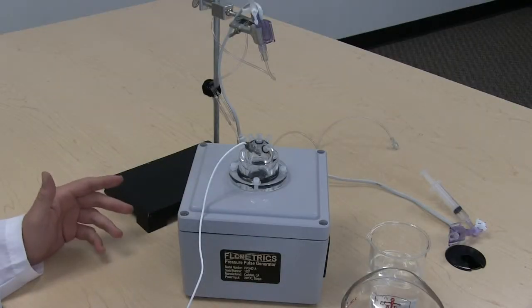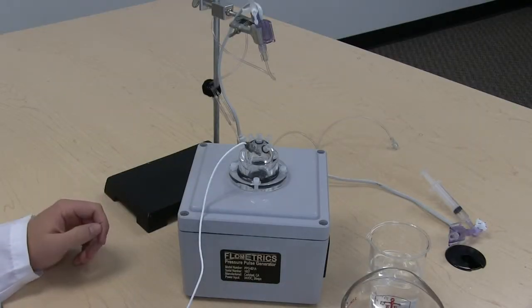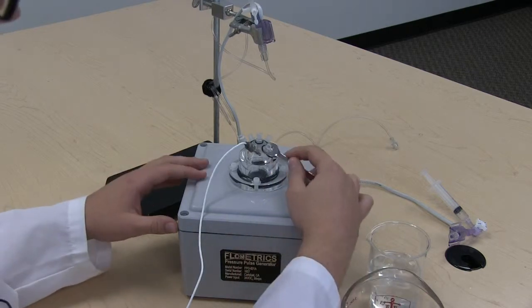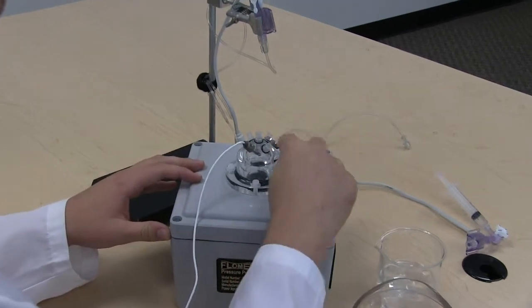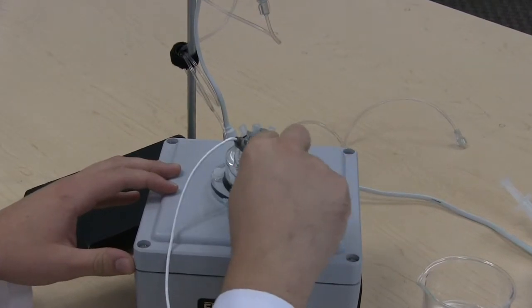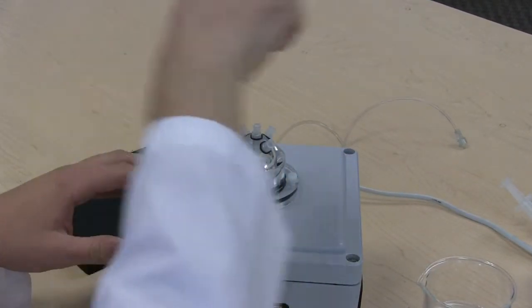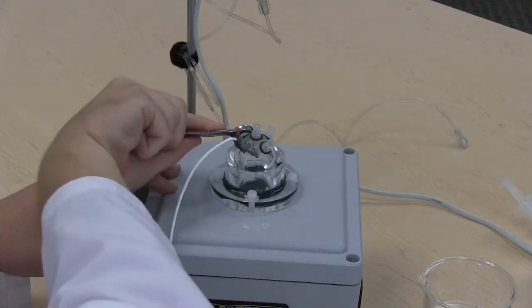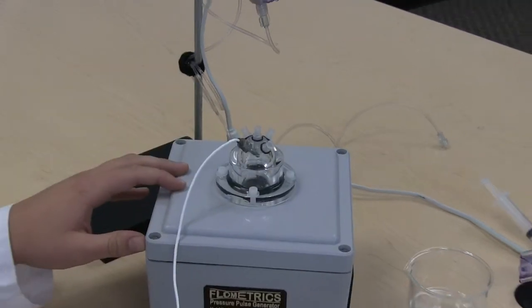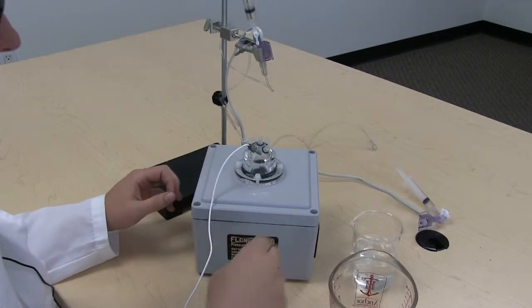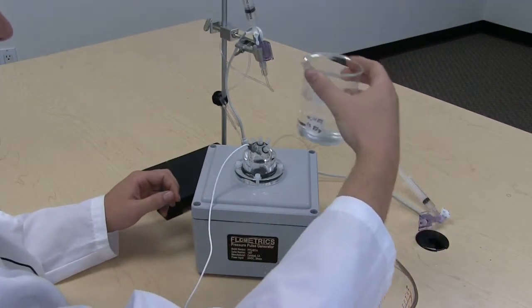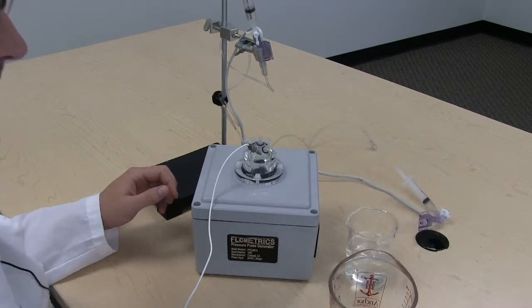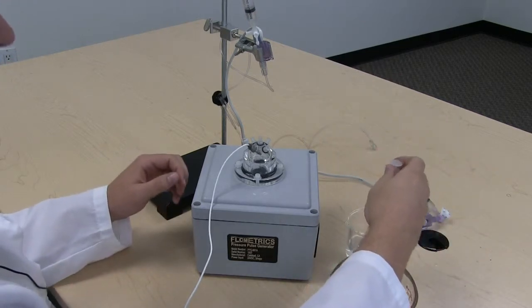So now we're going to fill the Flometrics pressure pulse generator. The first step is to make sure that all of the fittings are tight. Once you've tightened all the fittings, we'll start with some degassed water, and we're going to use a syringe to slowly fill the chamber.